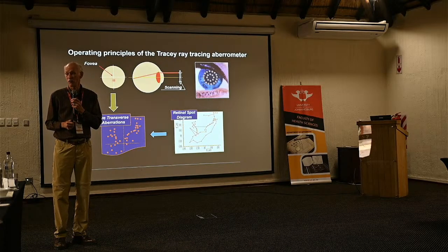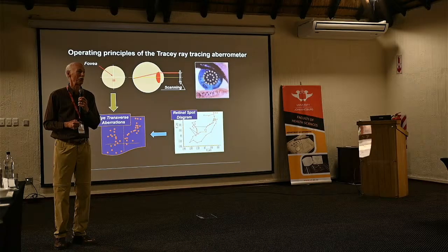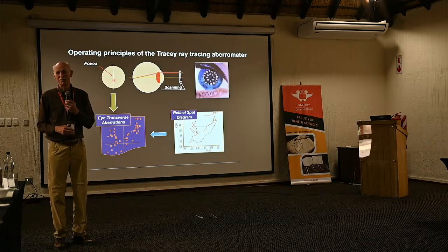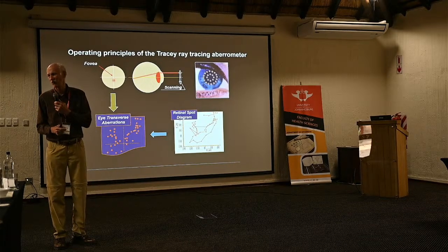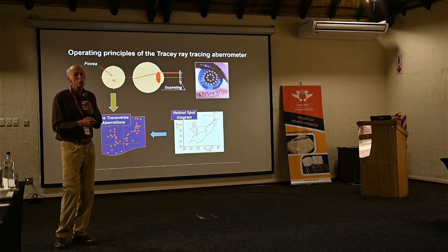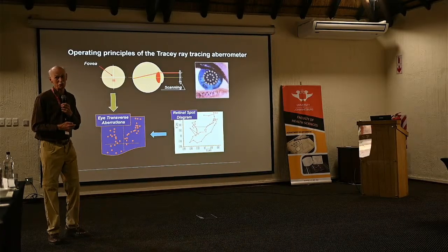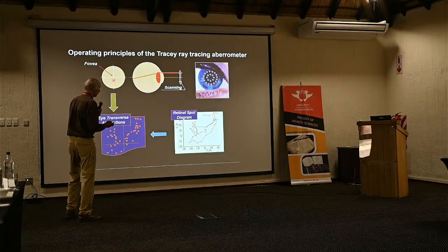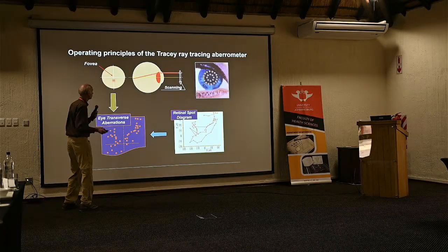Some instruments do that. And then when they're going to use it, what do they do? They differentiate the wavefront aberration function to get back to slopes. In a sense, you didn't really have to go to all that effort. You could have just stayed with the slopes. And in fact, it's possible to fit slopes with Zernike polynomials too. I didn't mention that, but you can do that. And you never ever have to measure the wavefront error function.